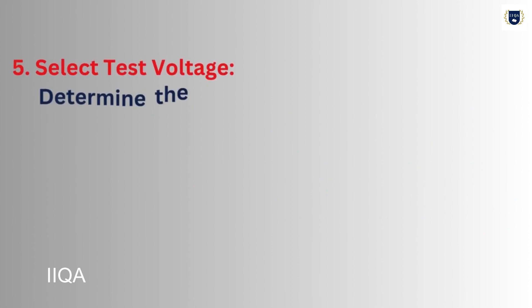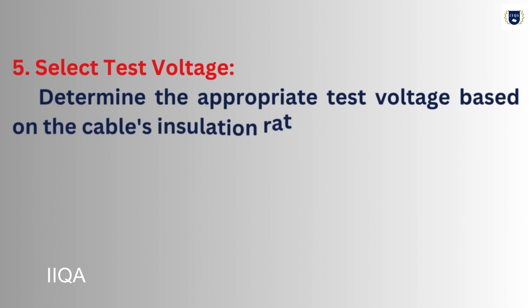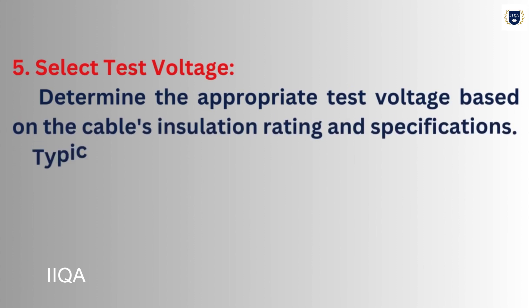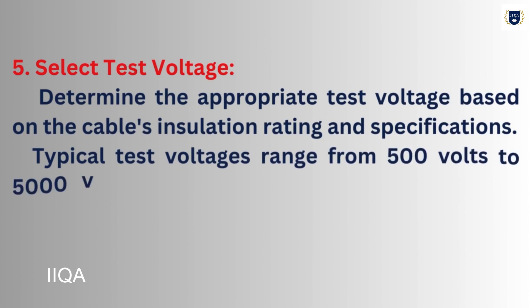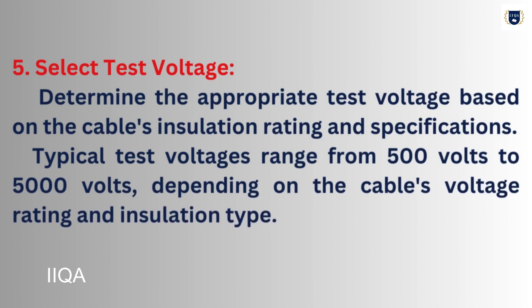Step 5 - Select Test Voltage: Determine the appropriate test voltage based on the cable's insulation rating and specifications. Typical test voltages range from 500 volts to 5000 volts, depending on the cable's voltage rating and insulation type.